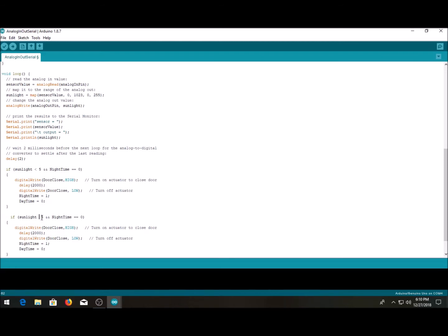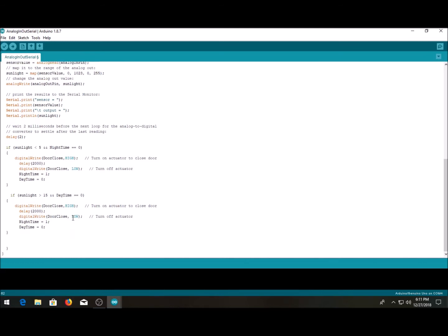Then we'll change this to if sunlight is greater than, and we'll use 15. Now we could use five, but when you put those variables too close, five and 15, then you're going to get a lot of strange behavior once you get to that point. So for this one we want to... This is saying that it's daytime now, so if daytime is equal to zero that would indicate that it's nighttime, so we're going to transition to daytime. Let's go ahead and put that in there and change this around.